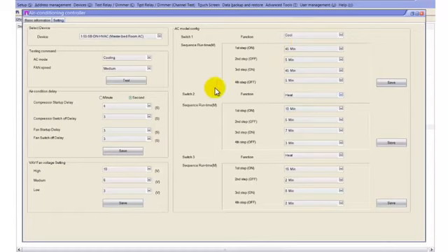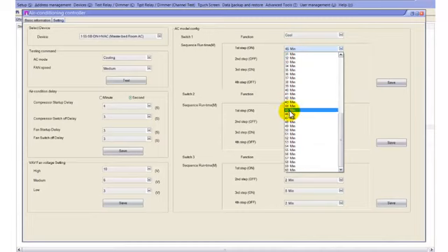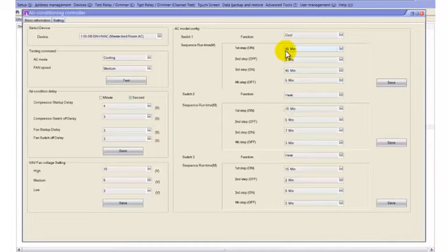We configure this, for example, if you run your AC on auto mode. We always keep the machine taking a rest for 5 to 10 minutes in a cycle, in a sequence. So what we can do is configure particular times here, like 45 minutes, so the AC will run for 45 minutes, then turn off for 5 minutes, again run for 45 minutes, and turn off for 5 minutes. We do this cycle only if you are using auto.